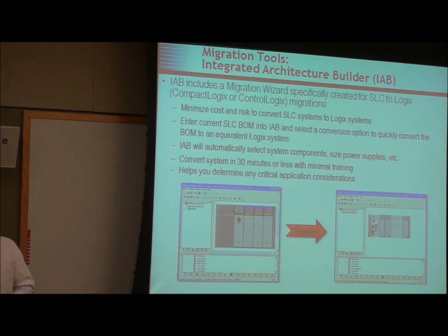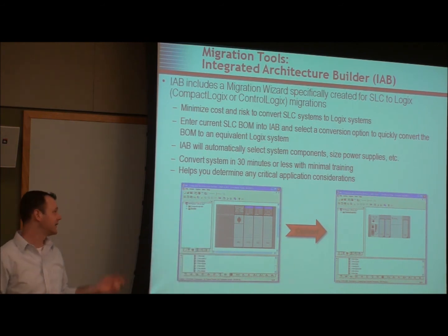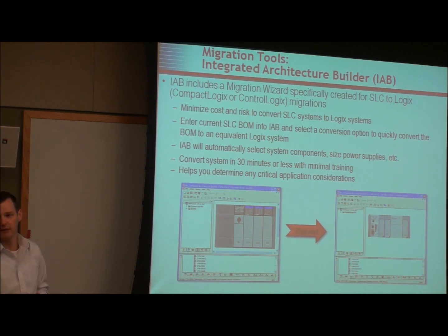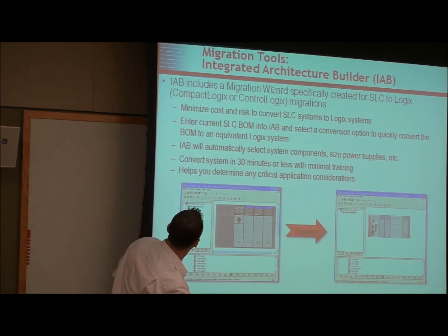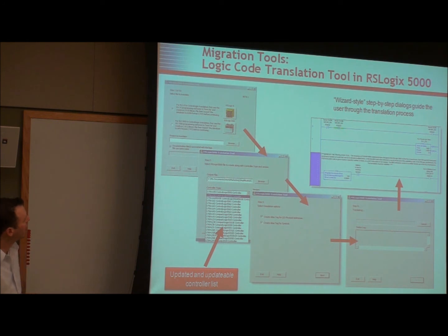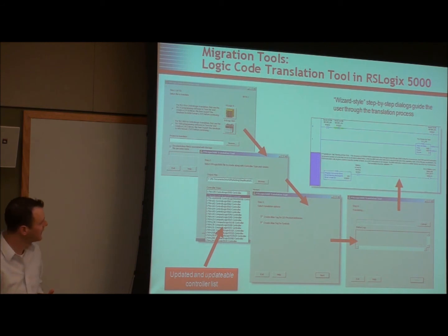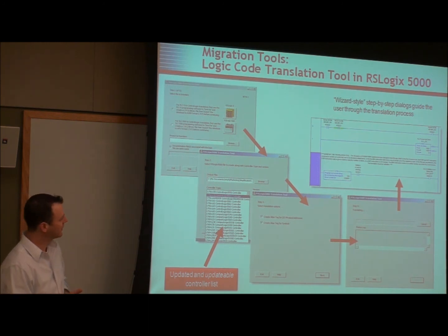In the Integrated Architecture Builder, there's a feature that lets you put in your current SLC system and tell it to convert. It will tell you which CompactLogix is equivalent to your SLC and give you a full bill of materials of everything you need to convert the system. There's also the code translation program that Matt spoke about — you can convert a PLC-5, SLC, or Micro program with it. It brings it into RSLogix 5000 and throws warnings and errors for anything that doesn't convert properly.